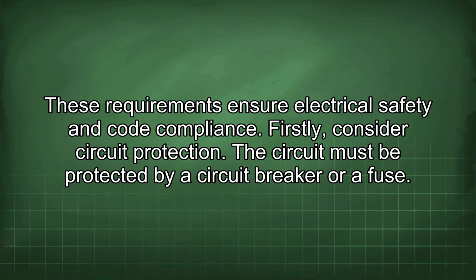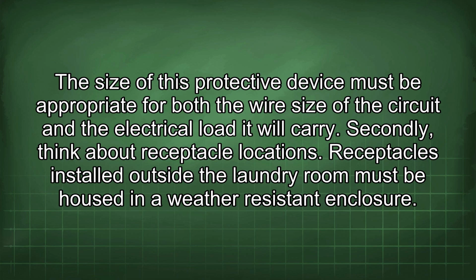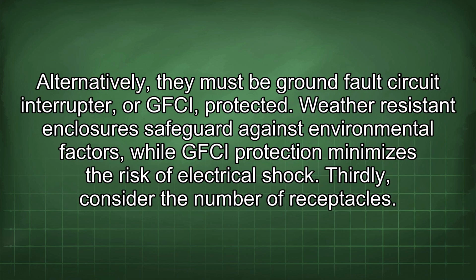Firstly, consider circuit protection. The circuit must be protected by a circuit breaker or a fuse. The size of this protective device must be appropriate for both the wire size of the circuit and the electrical load it will carry. Secondly, think about receptacle locations. Receptacles installed outside the laundry room must be housed in a weather-resistant enclosure. Alternatively, they must be ground fault circuit interrupter, or GFCI, protected. Weather-resistant enclosures safeguard against environmental factors, while GFCI protection minimizes the risk of electrical shock.